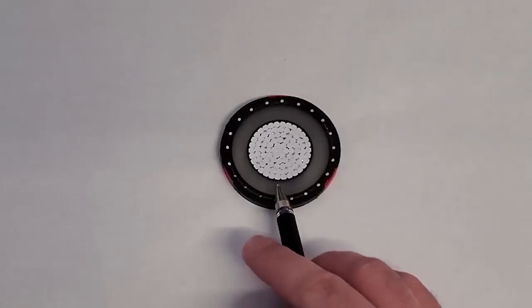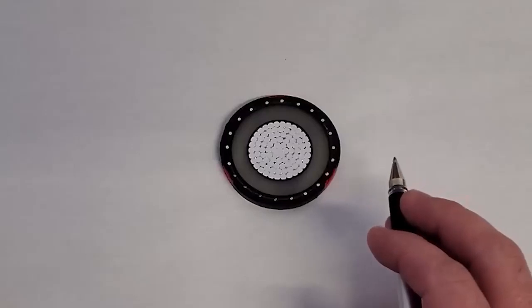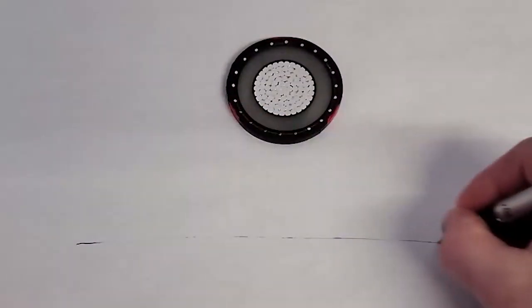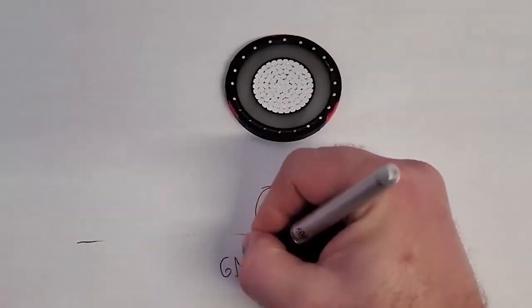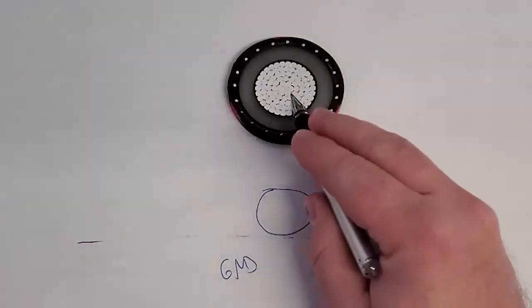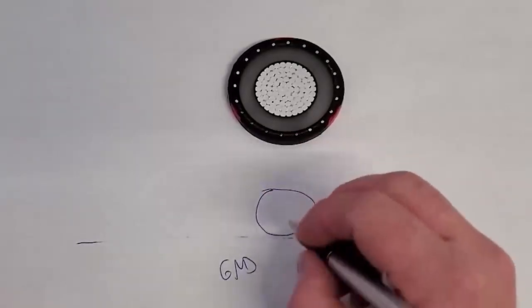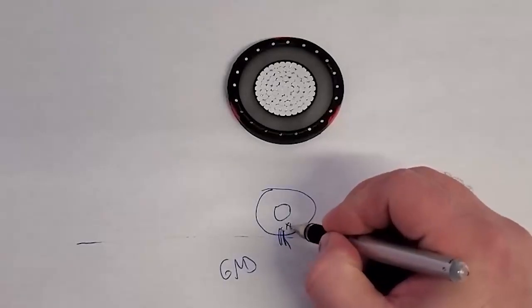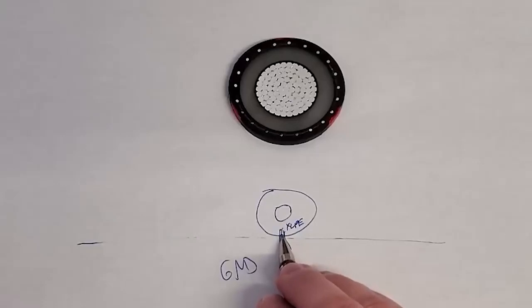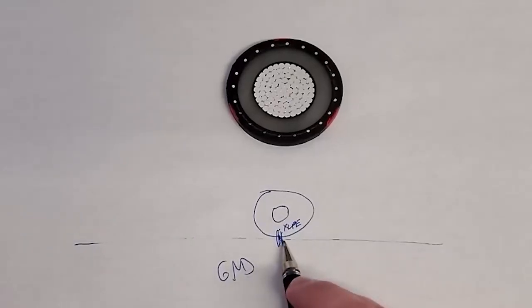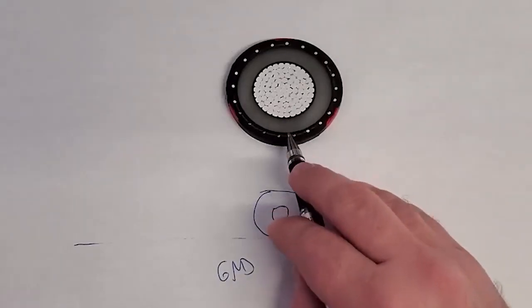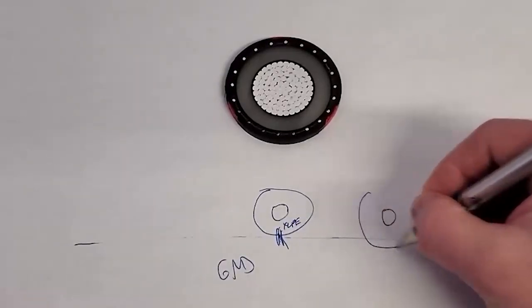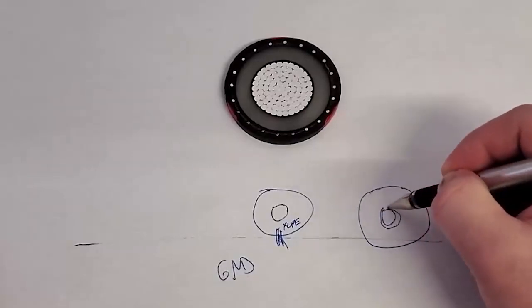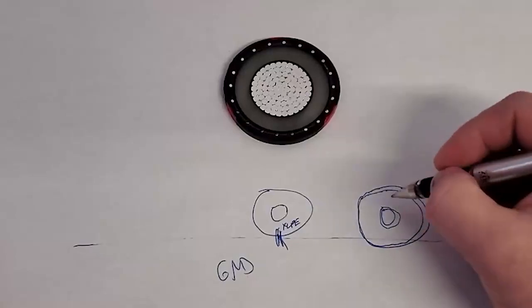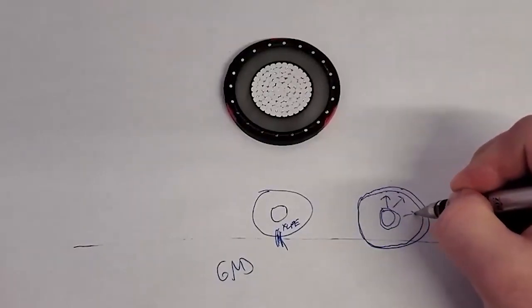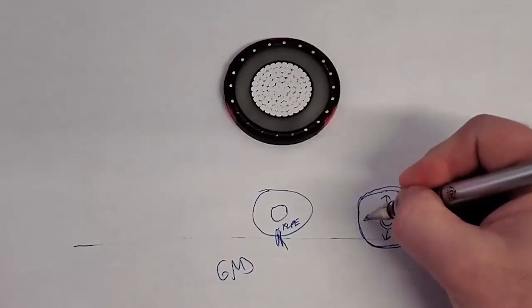So why do we need the semicon layer and that insulation shield? It's to prolong the life. So how is that? If you have a cable laying on the ground, right here, this is the ground, you're going to have bleed from the flux to ground. And if you do not have any of these layers, it's going to bleed right here. This is your conductor, this is your insulation, XLPE. It's all going to bleed through this part of the insulation, and it's going to break that insulation down over time. And that's what reduces the life of your cable. Going to this with the conductor shield and the insulation shield, same concept, but whether it's laying on the ground or not, with the insulation shield and that semicon layer, I'm a crappy drawer, everything's going to bleed evenly through that insulation to the semicon and to the concentric neutral layers.